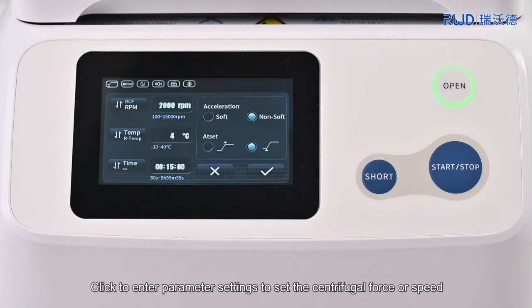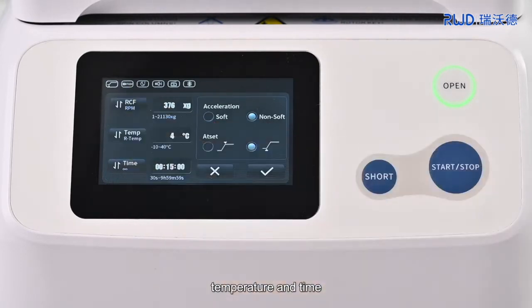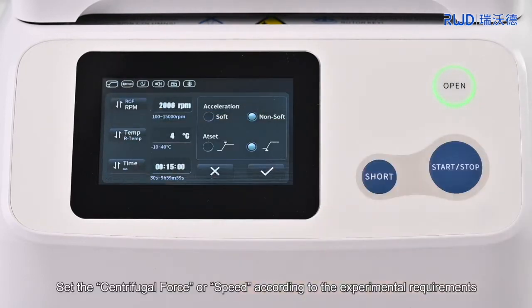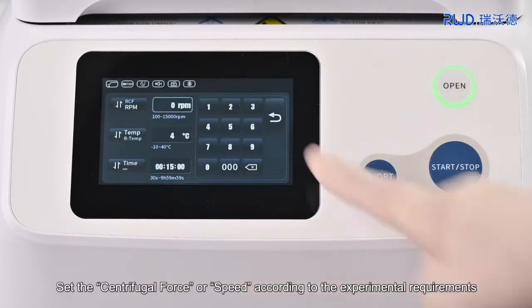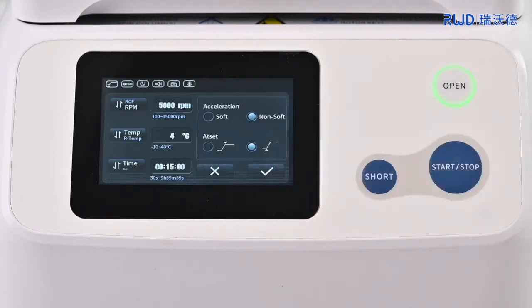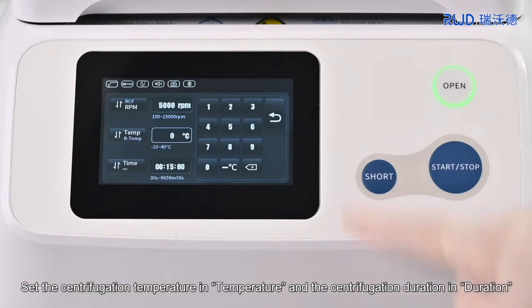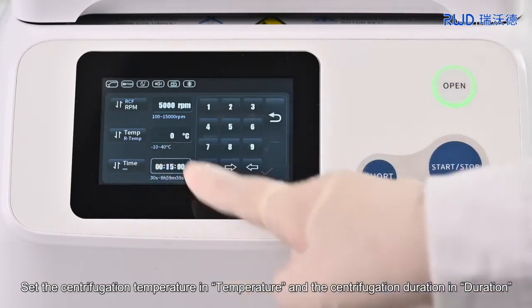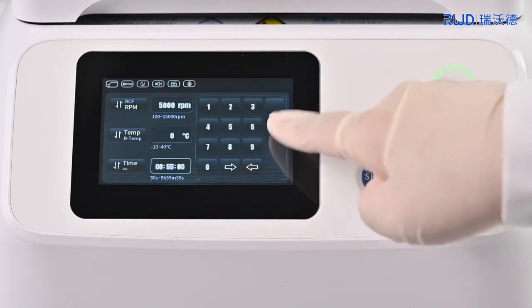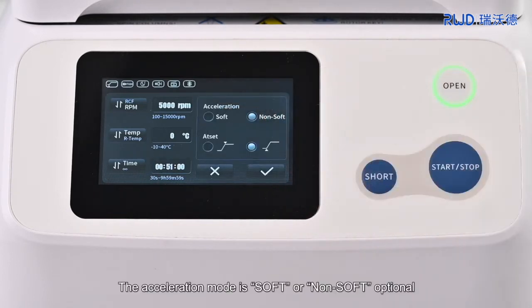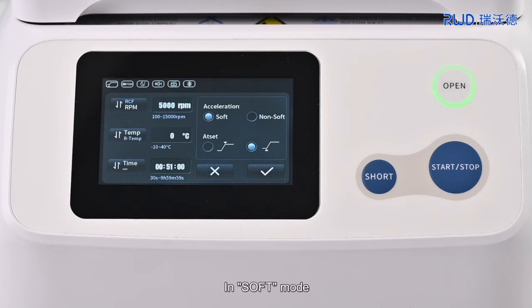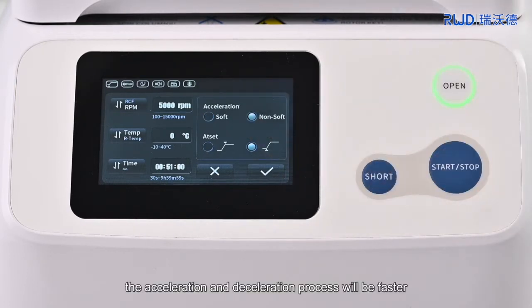Click to enter parameter settings to set the centrifugal force or speed, temperature, and time. Set the centrifugal force or speed according to the experimental requirements. Set the centrifugation temperature in temperature and the centrifugation duration in duration. The acceleration mode is soft or non-soft, optional. In soft mode, the acceleration and deceleration process will be more gentle. In non-soft mode, the acceleration and deceleration process will be faster.